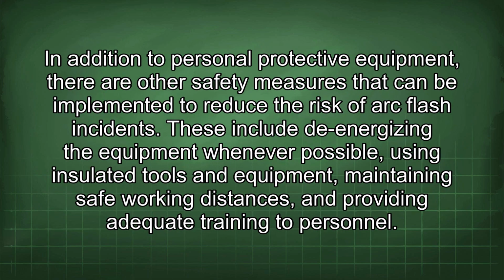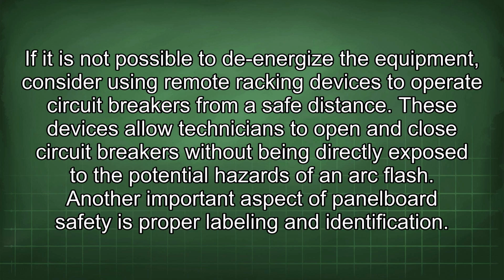In addition to personal protective equipment, there are other safety measures that can be implemented to reduce the risk of arc flash incidents. These include de-energizing the equipment whenever possible, using insulated tools and equipment, maintaining safe working distances, and providing adequate training to personnel. If it is not possible to de-energize the equipment, consider using remote racking devices to operate circuit breakers from a safe distance.